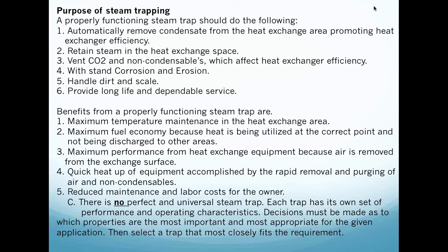If we cannot get the air and the non-condensables out of the steam space, then it's more difficult for us to get all of that space filled with steam and actually be able to extract the heat and put it into our air or our lumber or our paper or whatever it is that we're processing. The other thing that we sometimes have a difficult time with in our steam trap population is corrosion and erosion.